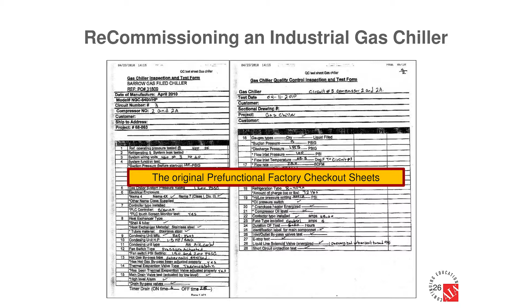This is the factory checkout sheet for one of the chillers. It talks about it being a 460-3 phase, that it had some NEMA 4X electronics, that it took so many pounds of refrigerant, and there's a page 2—and that's everything. So that was what we got. There was no pre-functional checkout of the installation itself.